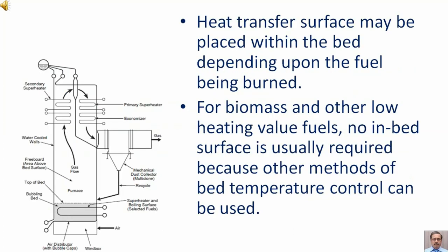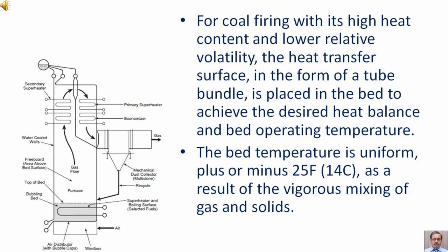Heat transfer surface may be placed within the bed depending upon the fuel being burned. For biomass and other low heating value fuels no in bed surface is usually required because other methods of bed temperature control can be used. For coal firing with its high heat content and lower relative volatility the heat transfer surface in the form of a tube bundle is placed in the bed to achieve the desired heat balance.